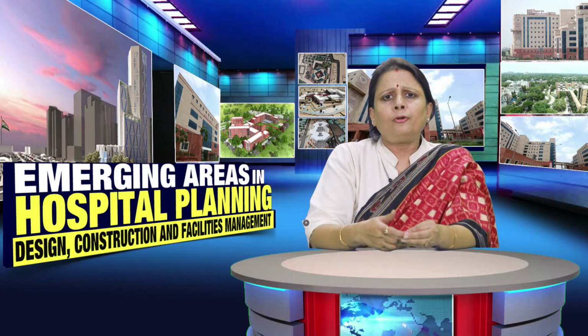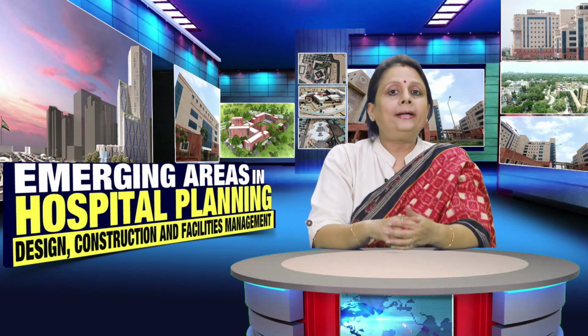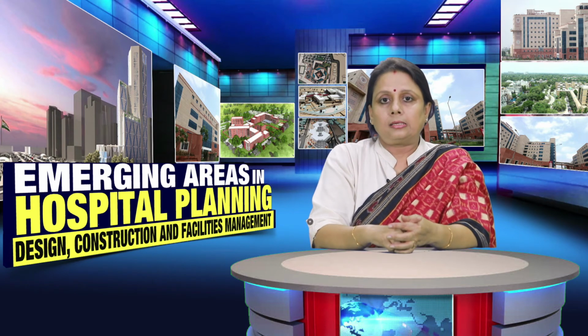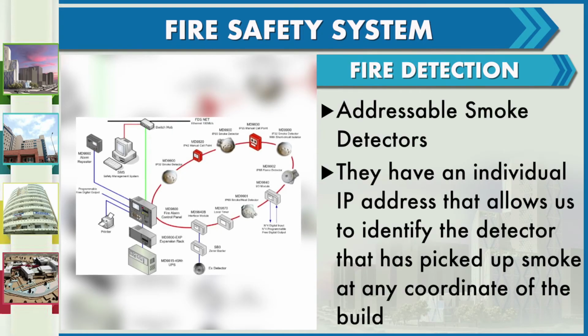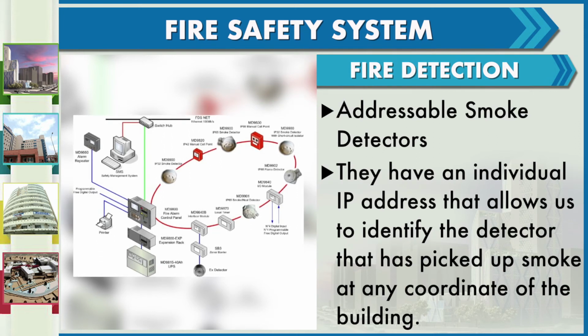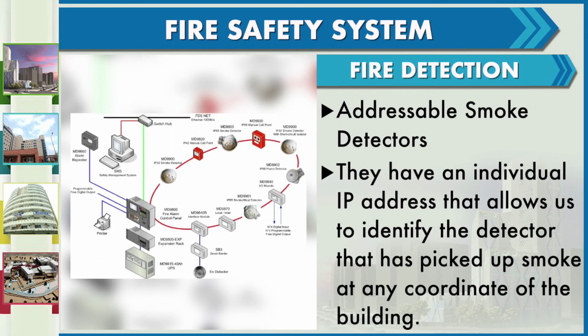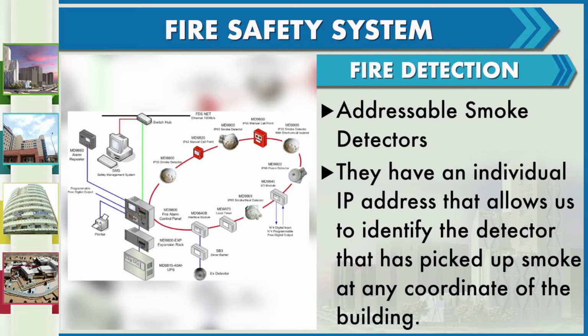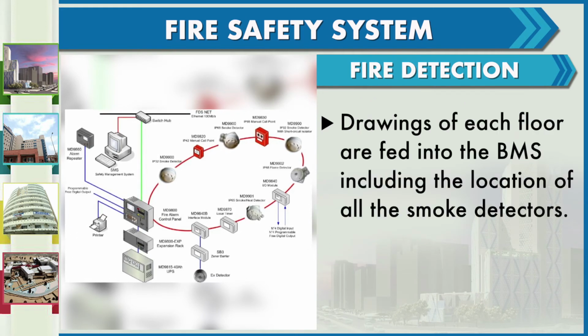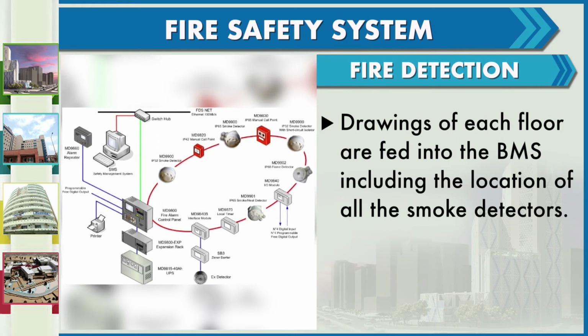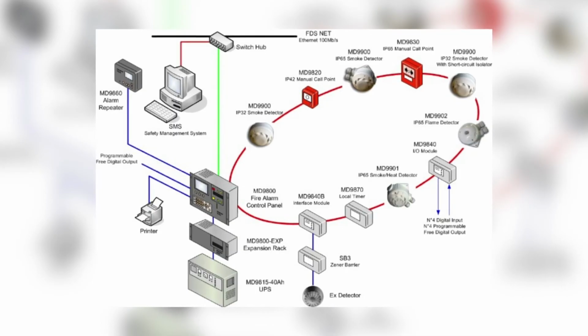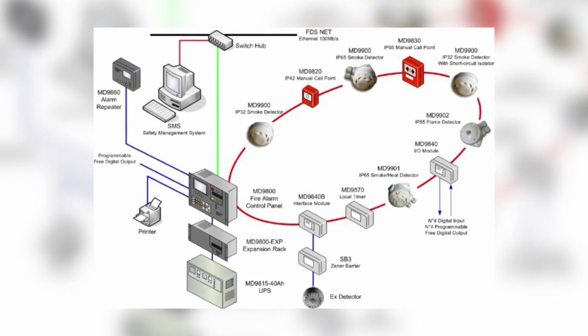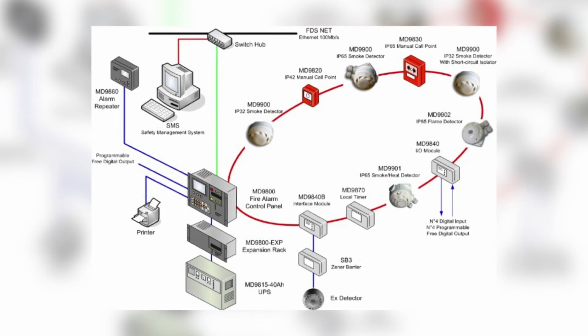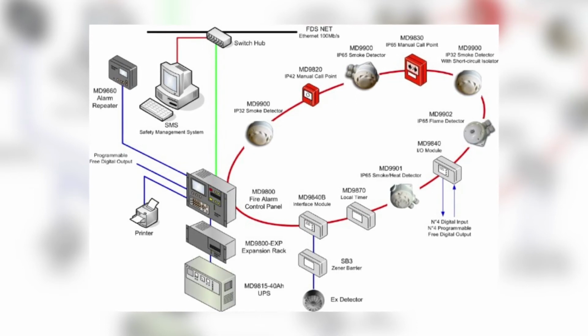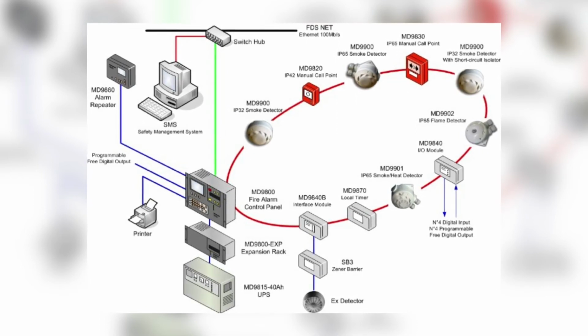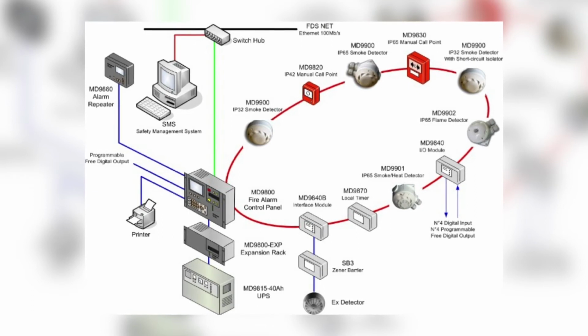For fire detection, we use addressable detectors with smoke or heat sensors. They have an individual IP address that allows us to identify the detector that has picked up smoke at any coordinate of the building. Drawings of each floor are fed into the BMS, including the location of all the smoke detectors. Network of smoke detectors runs across the building. The system is supplemented with manual call points at every interval. This whole network is managed with the help of BMS or Building Management System, which we will talk about later.